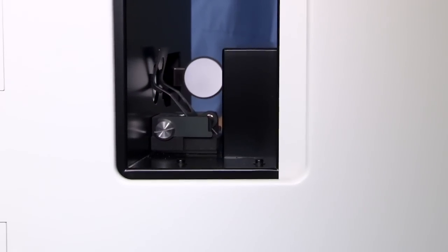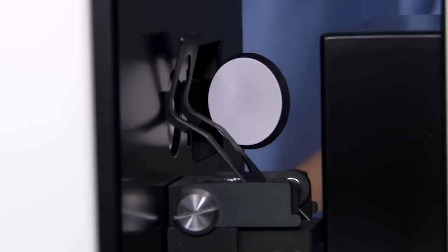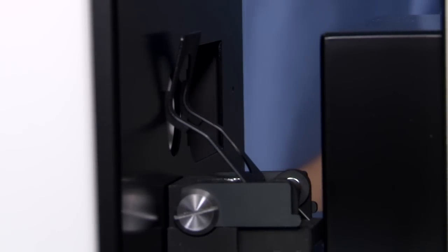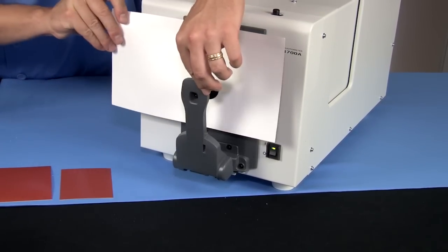Measurements made in SCE or specular component excluded mode are sensitive to surface conditions, ideal for use in quality control and visual evaluations to ensure the consistent appearance of products.